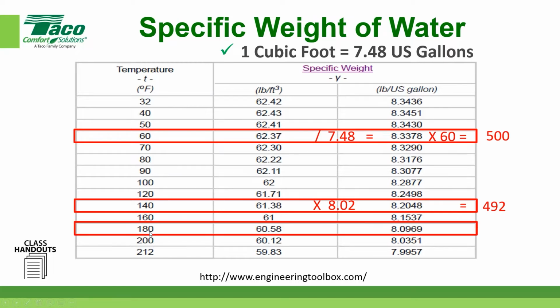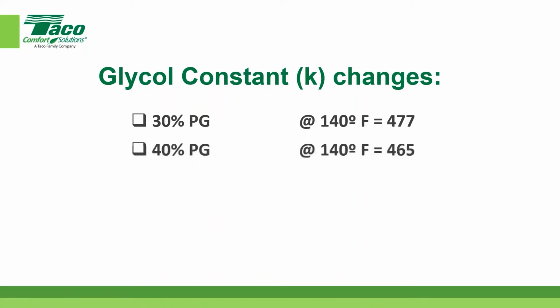And then let's go up to hotter fluid if we were using 180 and doing either the longhand or the shorthand version. You'll see that turns out to be 486. Now, what I want you to look at is 500, 492, 486. Look at what the number's actually doing. It's reducing its value. Look what happens when we talk about glycol, right? A 30% propylene glycol mix at 140 degrees is 477. And then if I do a 40%, it's 465. And if I do the good old college try 50%, it's basically 449, 450.